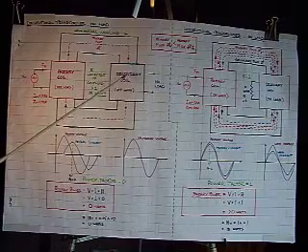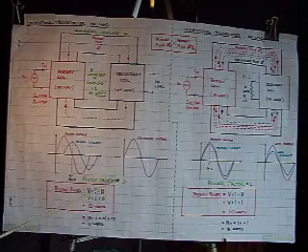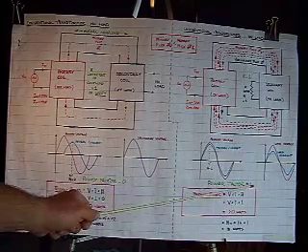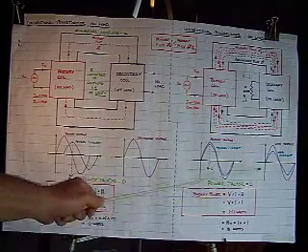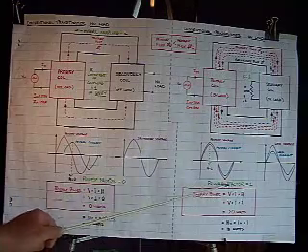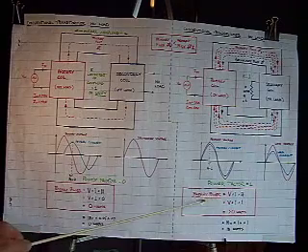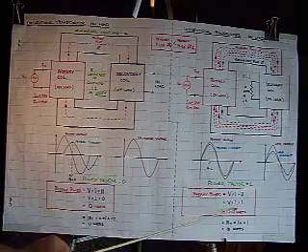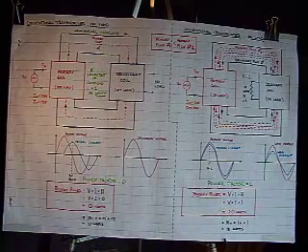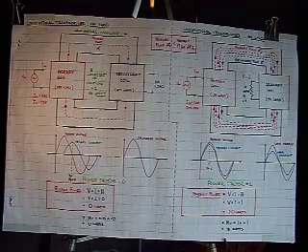delivers the no-load voltage. Again, with the conventional transformer on no load, the power factor is 0, and when it's on load, in this case a purely resistive load, the power factor of the load is transferred back to the primary, and in this case the power factor is 1. Now the primary power is the voltage times the current times the power factor, and the power factor is 1, so we have real power being consumed by the primary coil and real power being delivered by the secondary coil.